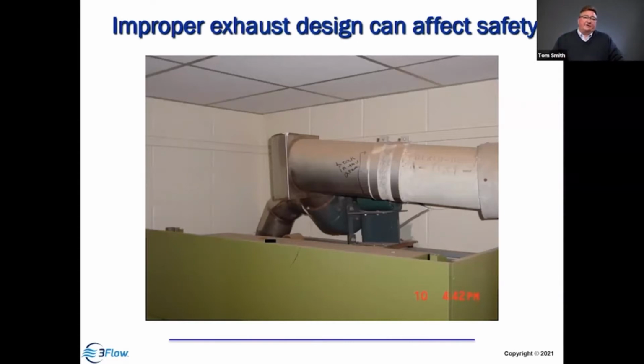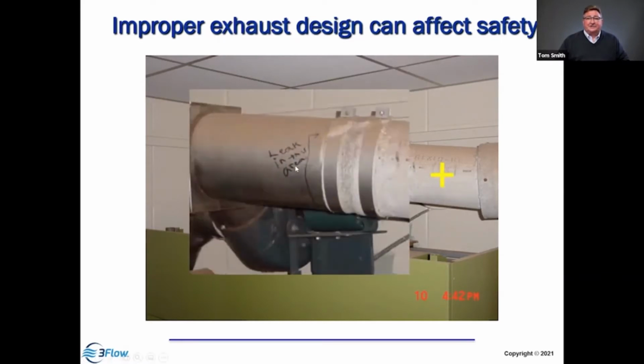Another example is a hood we got called in to test because people were using it with some ether and they could smell the ether and were saying something's not right. So I came in to take a look at this hood. As we were testing it, sure enough, it failed the tracer gas test, and we could detect it in the space. When I got on the ladder and looked above, I saw it had an exhaust fan right above the hood blowing the air down the duct. Then I noticed that something had been written on the duct. It said, leaks in this area. So I said, well, here's the problem. In this case, the positively pressurized duct downstream was not adequate to provide containment and removal of the materials, and so we were getting some escape.